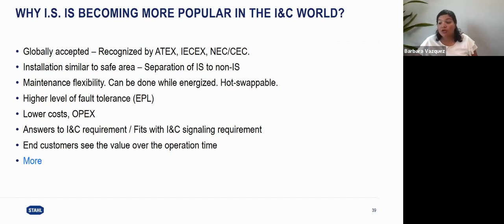So being able to replace the card or replace the field device for troubleshooting while everything is energized makes the maintenance way faster, which creates savings for operations. Definitely the fact that intrinsic safety, when it's done properly, of course, has that level of tolerance to independent faults and your system is still safe. And also for instrumentation, which is what we are mainly talking about today, instruments require a lower amount of energy to work, right? 24 volts, 50 milliamps, something like that. So it's easier for manufacturers to build intrinsically safe instrumentation.